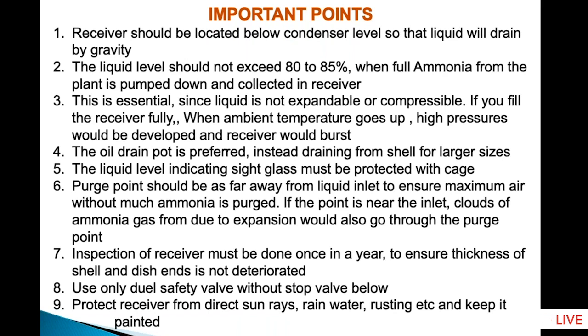Inspection of the receiver must be done once a year to ensure that the thickness of the shell as well as the dish ends has not deteriorated. For this you need not empty the receiver. Now thickness gauges are available and you can measure the thickness when the vessel is in operation.